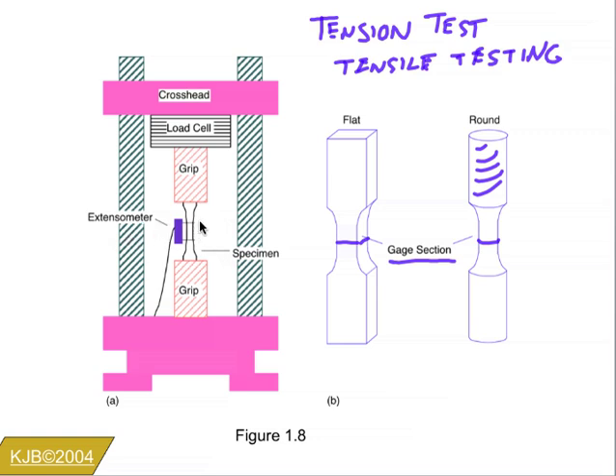Often an extensometer is used. It can be an extensometer that measures the change in length, or it can be one that measures the change in diameter. Obviously, measuring the change in length involves more sensitivity, but we can have either one. It can be a diameter gauge or an extension gauge, and that gauge allows us to directly measure the displacement within this area. Otherwise, there's going to be displacement from elastic distortion, bending of the crosshead, and these that we'd have to account for or actually subtract for in order to verify what's taking place.